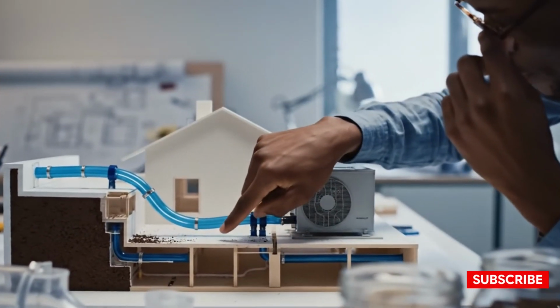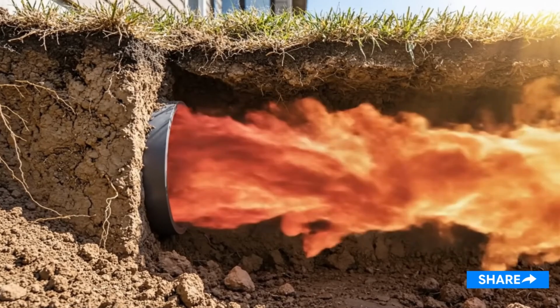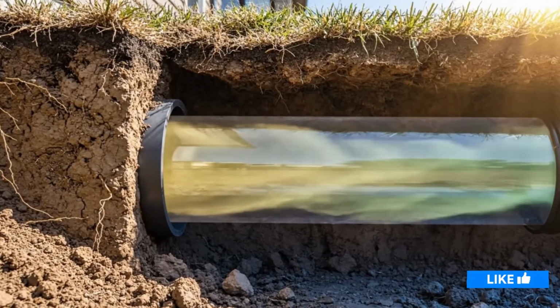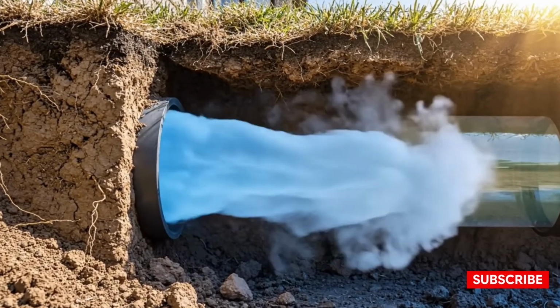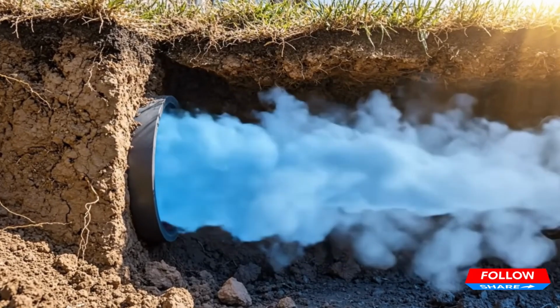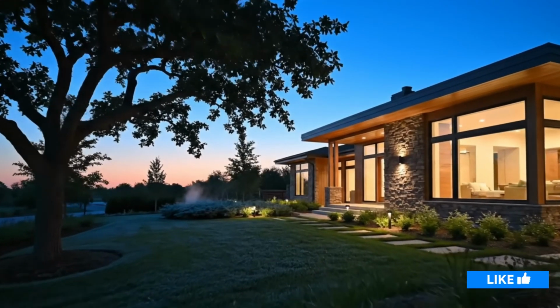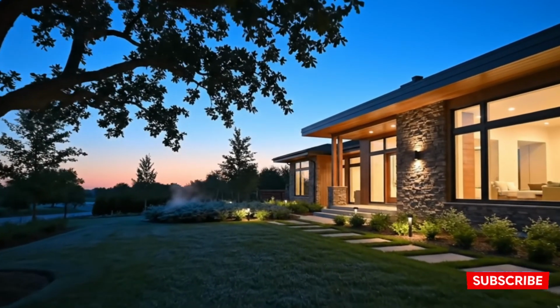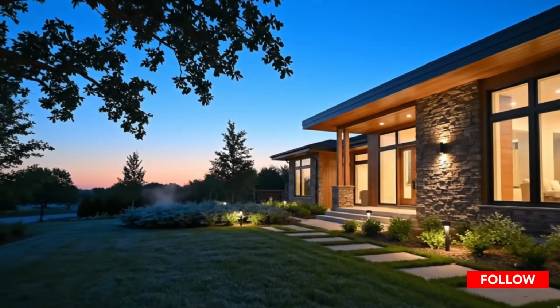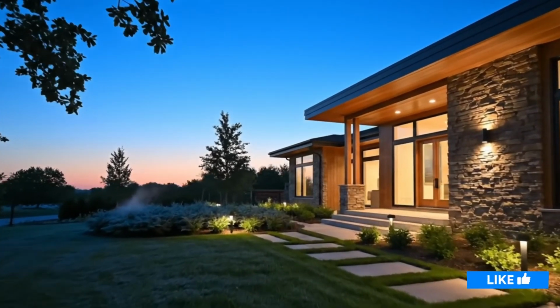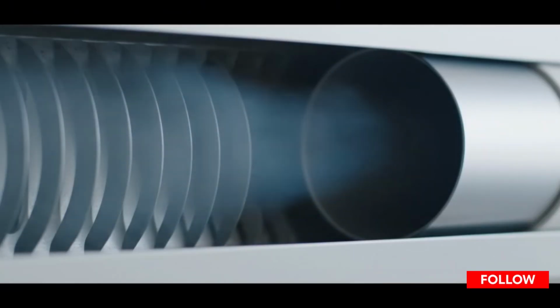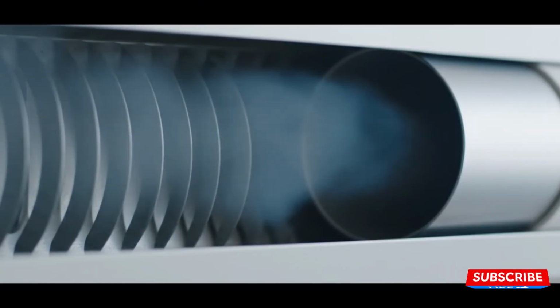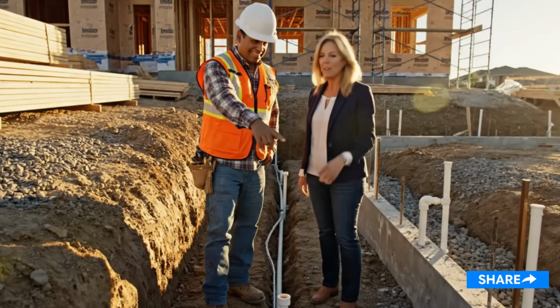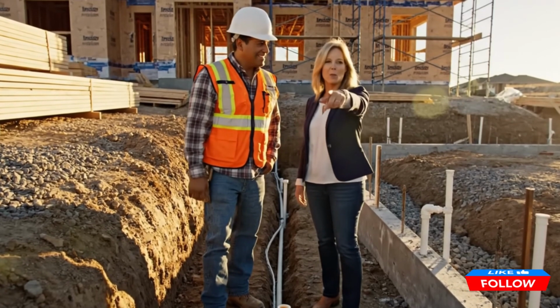In many US states, earth tubes aren't explicitly and directly banned. And what happens in practice tends to be more frustrating. They simply fall outside any clear framework. Building codes often don't include a clear section explaining how a residential underground air heat exchange system should be designed, tested, approved, inspected, or maintained. And when the code doesn't offer a defined path, inspectors tend to say no, not because the physics is wrong, not because the system can't work, but because almost no one wants to approve something that falls outside the most familiar technical language.